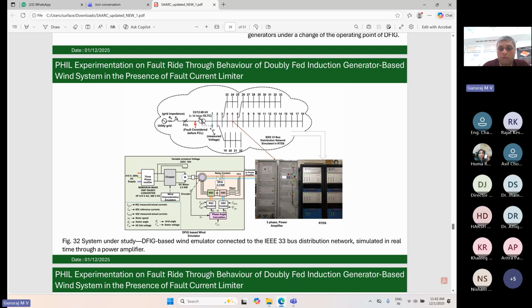Henceforth, a huge amount of voltage or magnetization is being induced on the rotor side. But the converters are not rated up to that capacity, so that will damage the converters, switches, and DC link capacitor. Overall, the system becomes quite unstable. This is what we call fault ride-through.